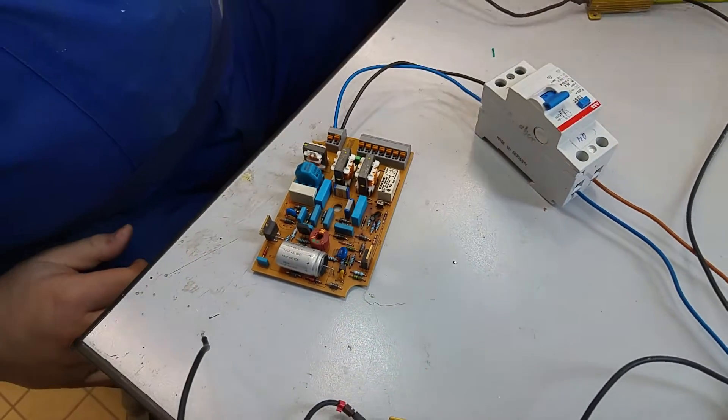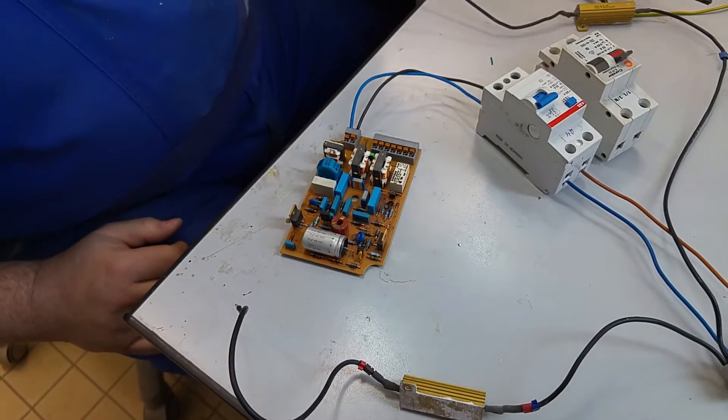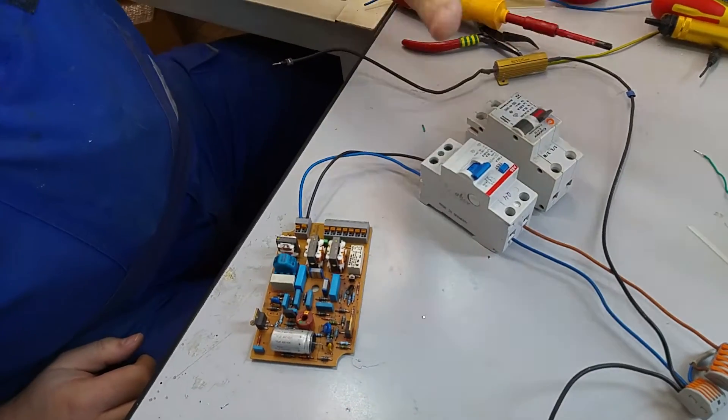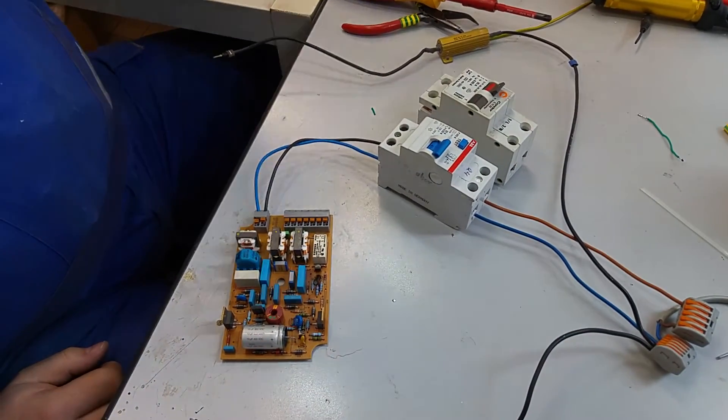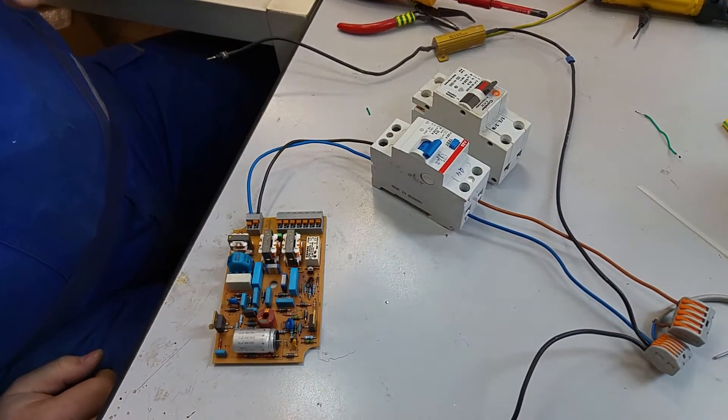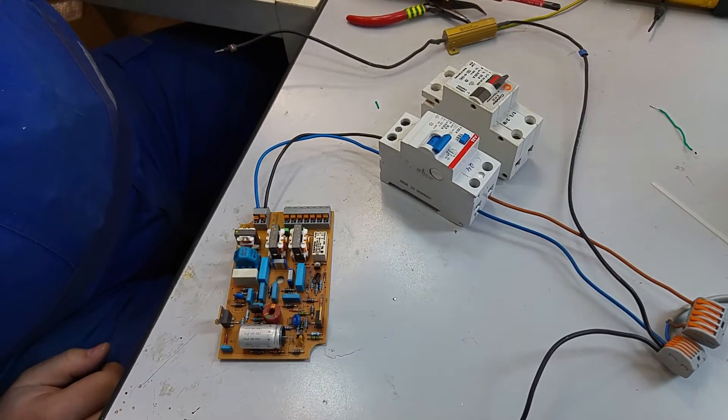So this RCD, it's perfectly the same, it has the same markings, anything. It's a bit newer and it doesn't trip at all with DC.